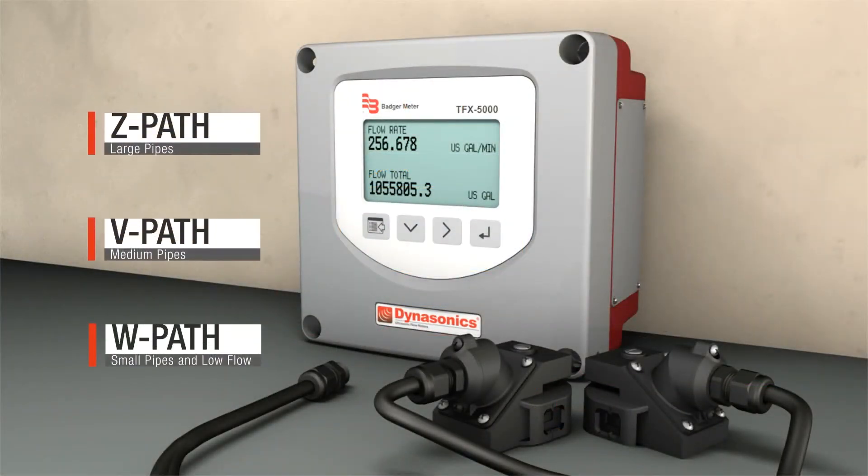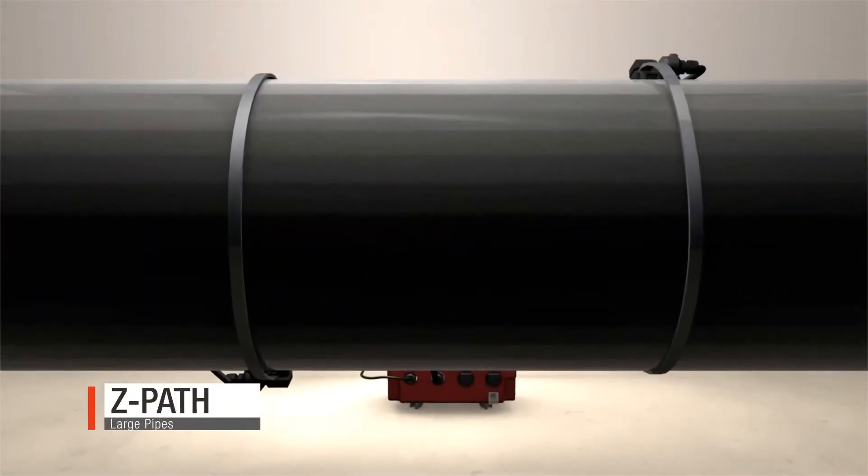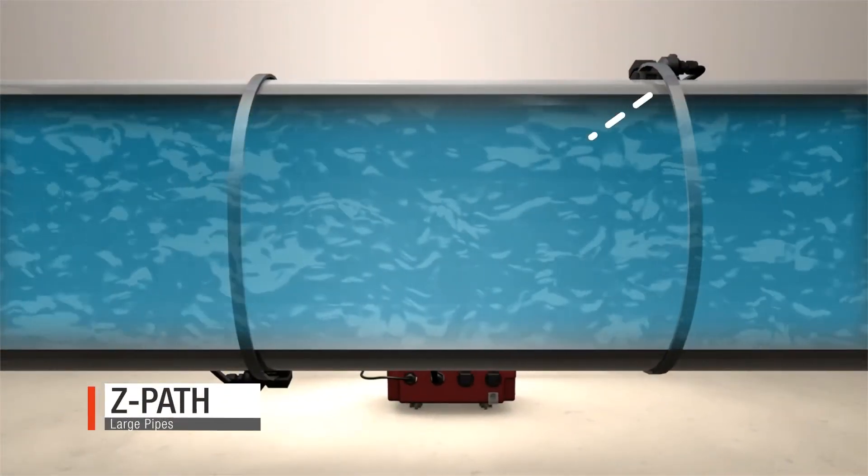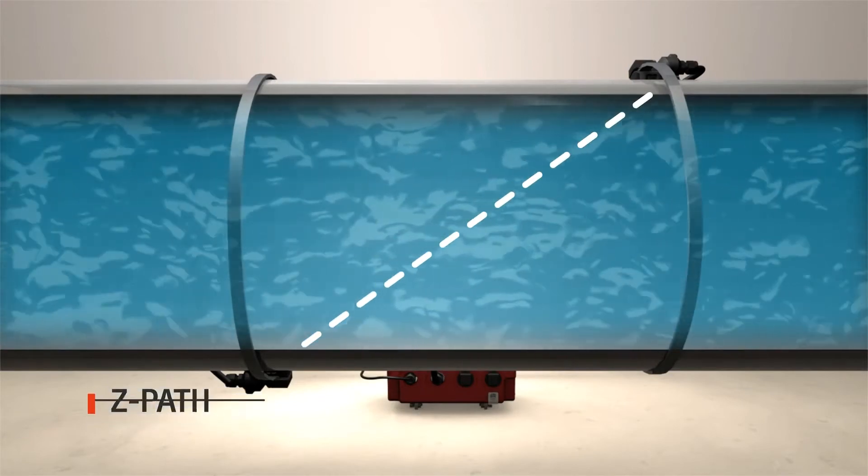Clamp-on transducers can be positioned in multiple ways. A Z path or 1 traverse is typically used on large pipes. The signal is strongest when it travels this type of path.